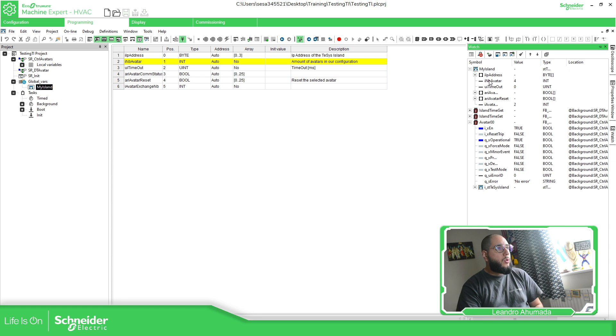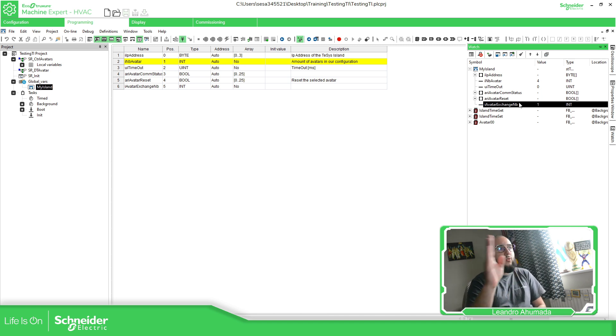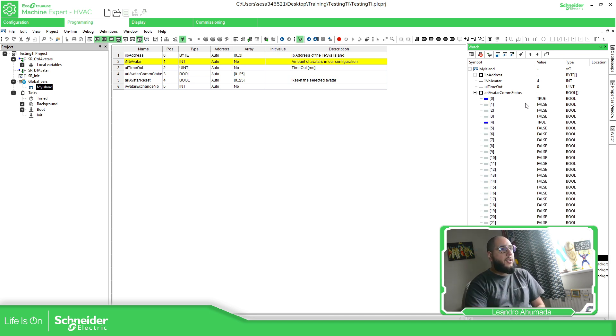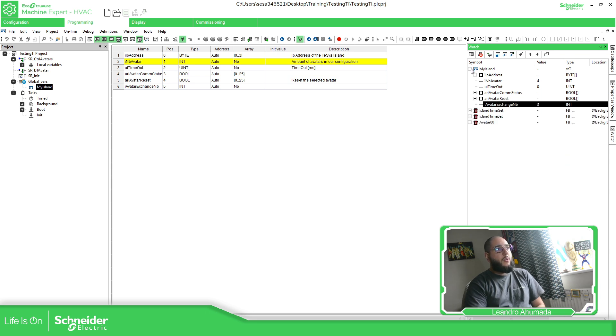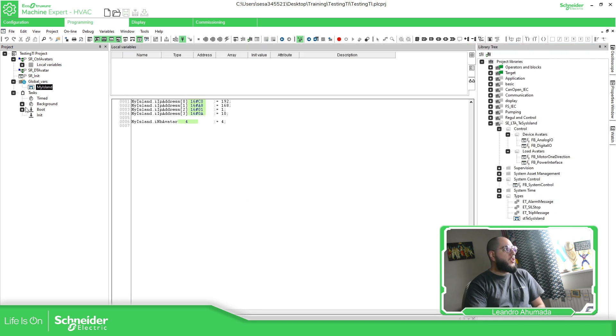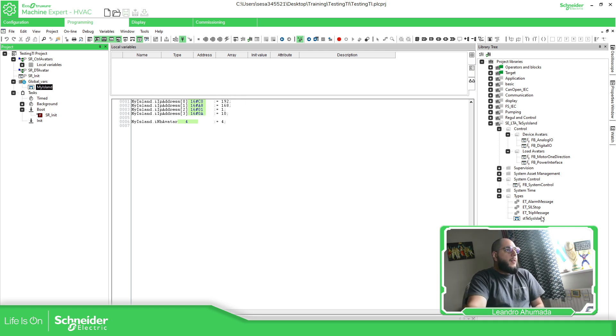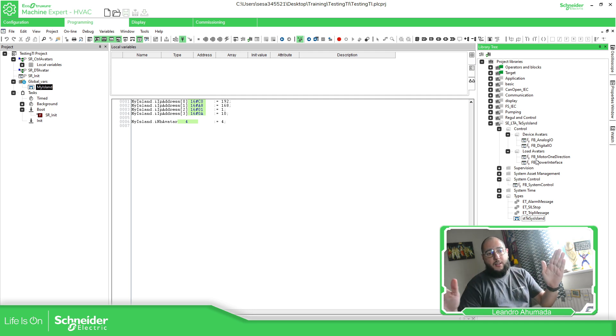If you take a look in the watch, you can see there is an avatar exchange number cycling: one, two, three, four — repeatedly. That is the indication of the communication cycling through all of them. I follow that sequence, and I have an initial function block on boot just to define the IP address and the number of avatars. I created a sequence to read each of the avatars, and within each avatar I have my own sequence to read and write the information. In the control avatars view, you can see there is no error whatsoever — system control is already done and covered.